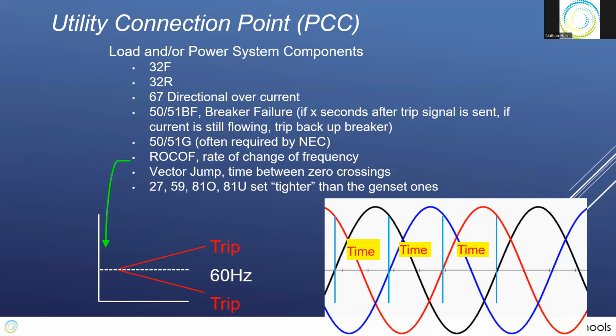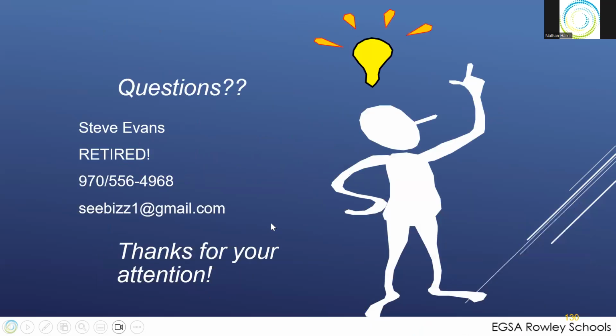Vector jump is very, very fast, very quick, very good protection, but almost too much. It measures the time between each zero crossing and says, if that time changes too much, I'm going to trip. Something happened to my grid. And so it's not used often because it is so sensitive. And then the 27, 59, 81O, 81U are set tighter. So under voltage, over voltage, under/over frequency are set a little tighter.